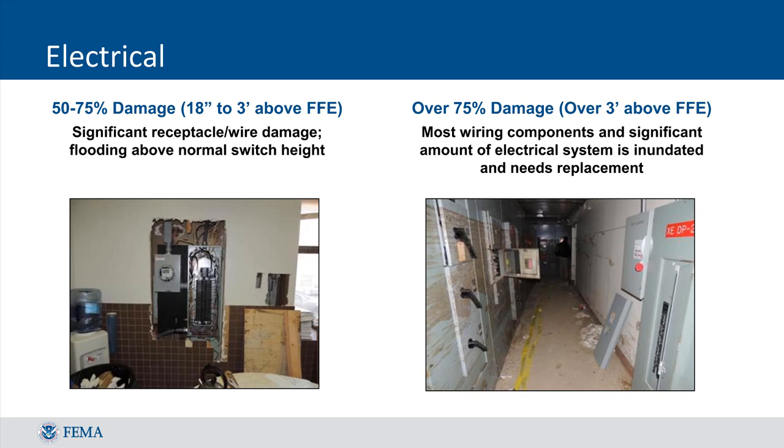The photo to the right shows a switchgear system that was completely flooded by over 5 feet of water. This level of damage would fall into the over 75% range due to the level of replacement that would be necessary within the entire electrical system.